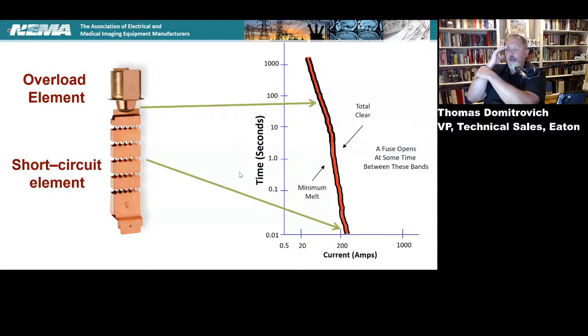And that's how when I think about a fuse curve, when you tell me a class L, you tell me a time delay or fast acting, class J, or class H, in my mind, I'm picturing these fuse curves, because every one of those different classifications, every one of those different types of fuses, even within a specific class, is basically giving you a shape of a curve that you need to understand for the reasons of what Jack pointed out with motors and the inrush current. You got to think about that.